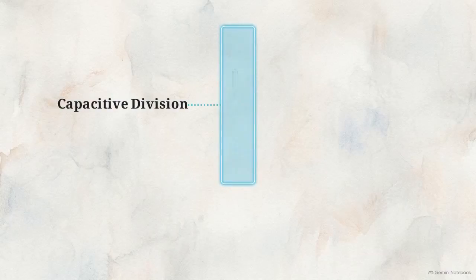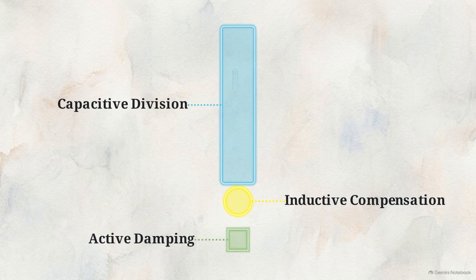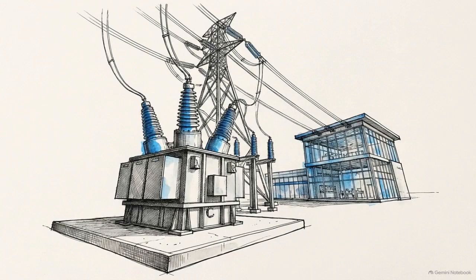By coordinating capacitive division, inductive compensation, and active damping, the CVT maintains measurement integrity even under volatile grid conditions. This specialized architecture is what allows 765 kV measurements to be both safe and precise, turning raw transmission potential into manageable, readable data for grid operators.